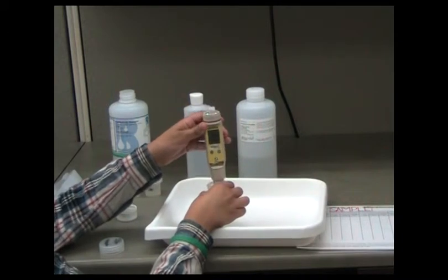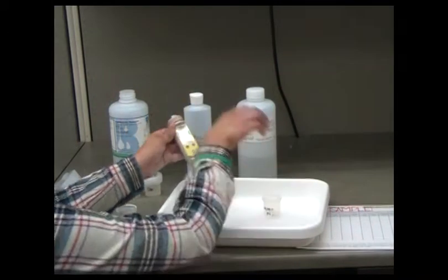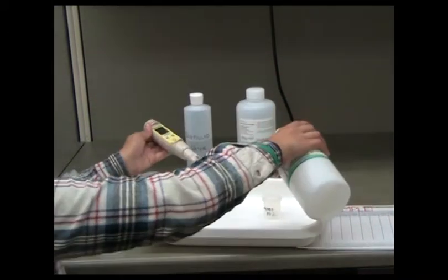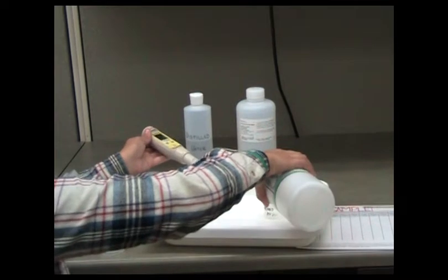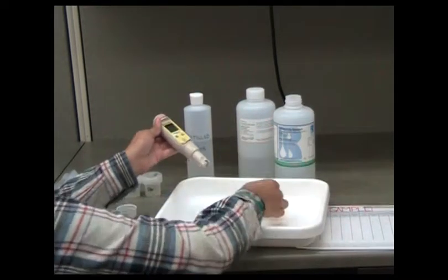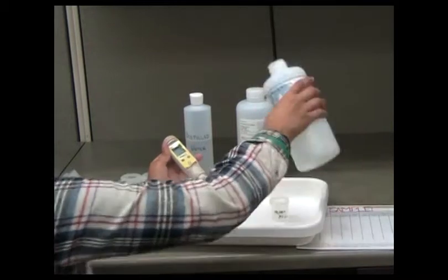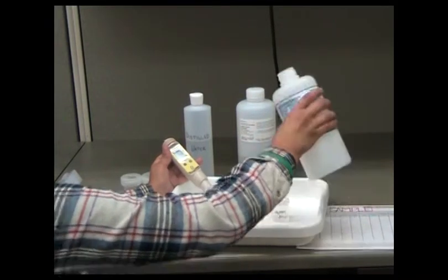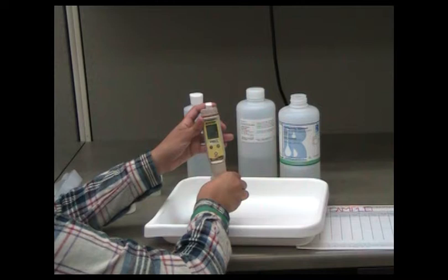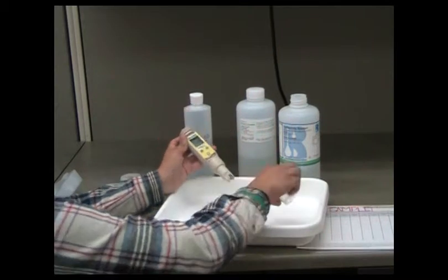Rinse the electrode in the high standard solution of 10,000 microsiemens per centimeter. Rinse it three times in a 30-milliliter Nalgene jar and pour out the standard into the waste tray between each rinse. Fill the jar a fourth time and submerge the probe in the solution.